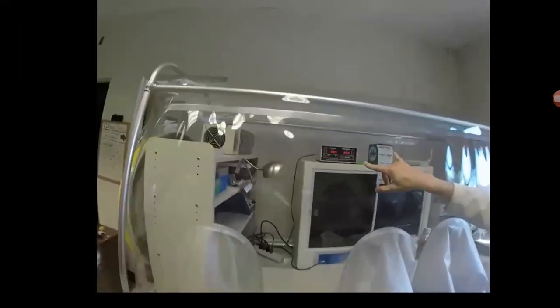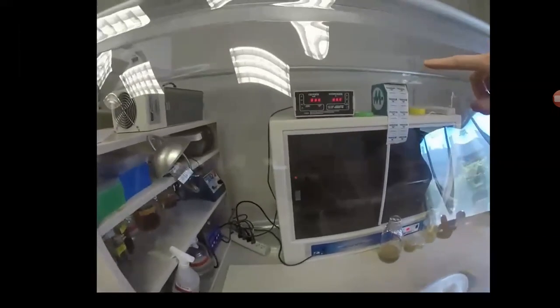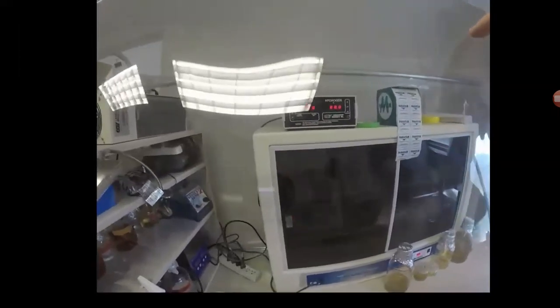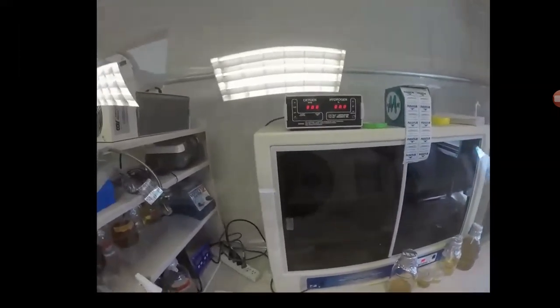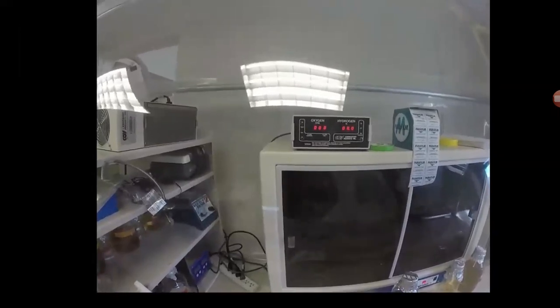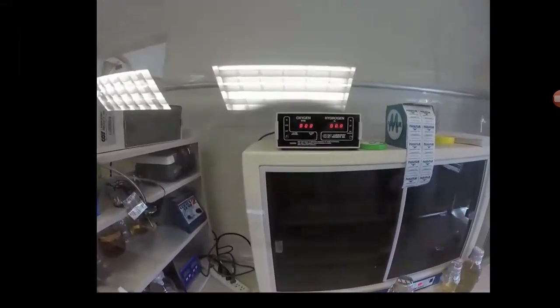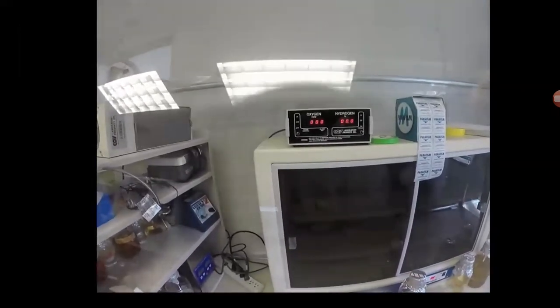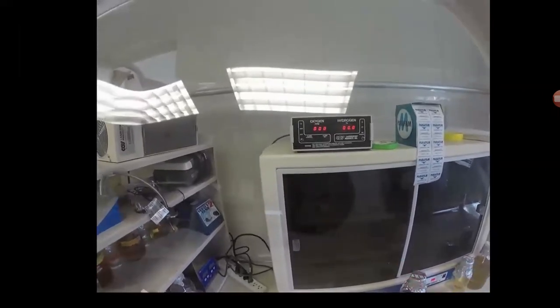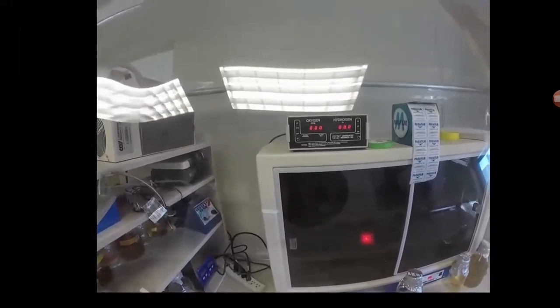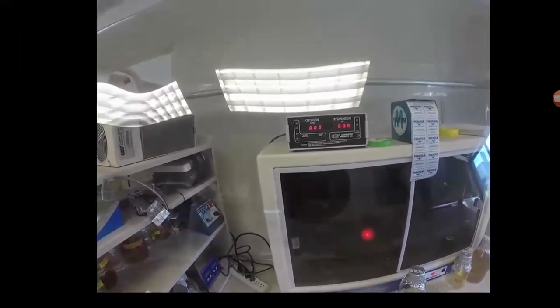If you look inside, the first thing you can see probably is there's a sensor there. That sensor is just indicating to you the oxygen concentration on the left and the hydrogen concentration on the right. As you can see at the moment, they're both 0, which is actually problematic. So oxygen should be 0. That means that we're anaerobic, but hydrogen needs to be somewhere around 1 to 2%.